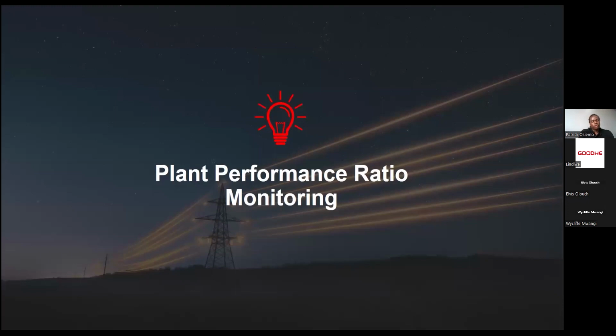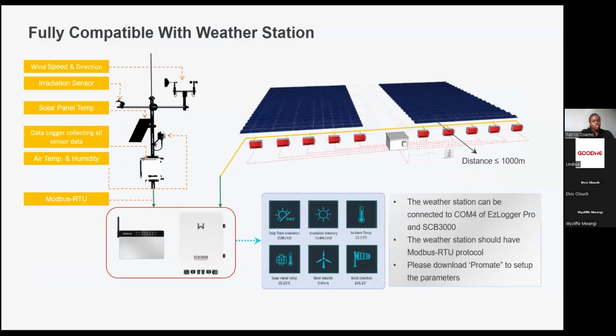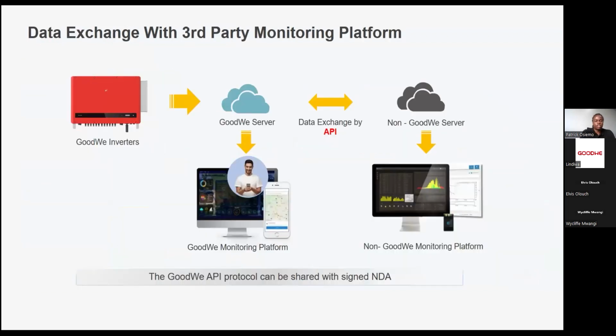In case you want plant performance ratio, the PR, most of our clients do want assurance on the PR, and GoodWe also allows this. How is this achieved? The Easy Logger is compatible with third-party monitoring weather stations. The weather station should communicate through RS-485, so the Modbus RTU protocol needs to be observed. The weather station can carry all kinds of sensors: wind speed, irradiance, data logger, air temperature, humidity. All those weather conditions can be monitored once you take the Easy Logger and link it to your plant. So yes, you can do the PR monitoring once the weather conditions are integrated with your plant.